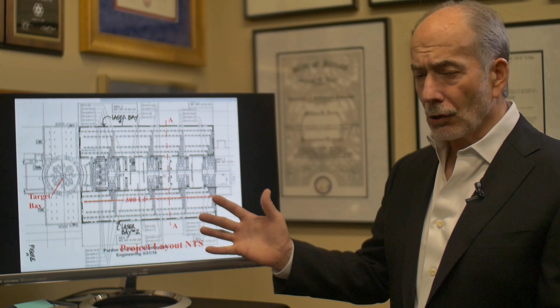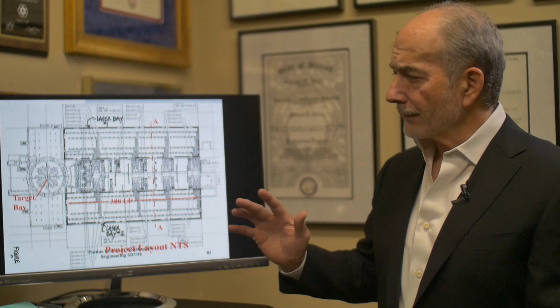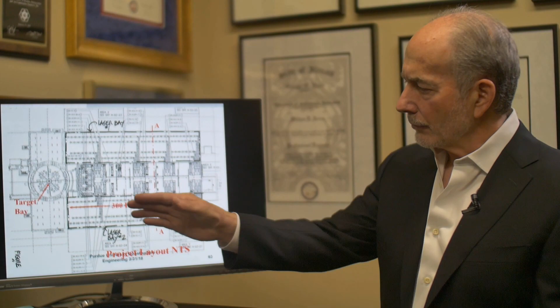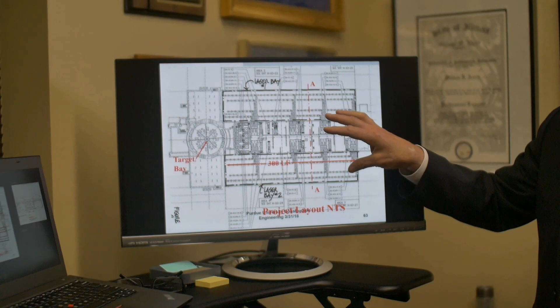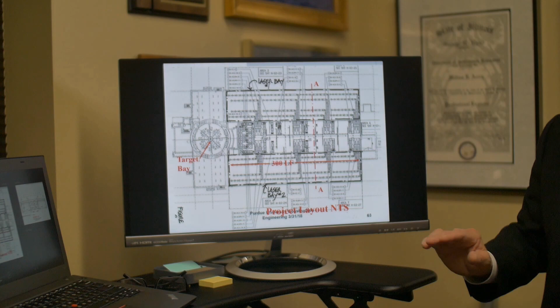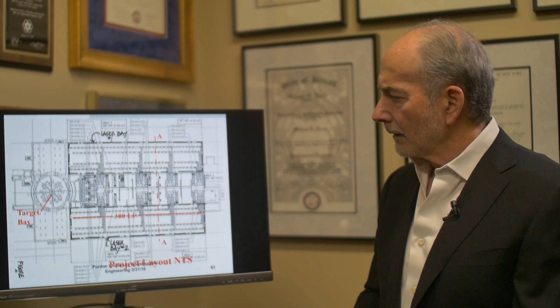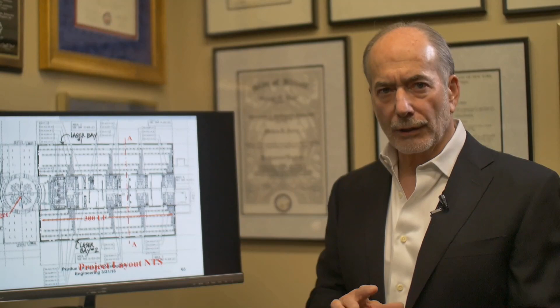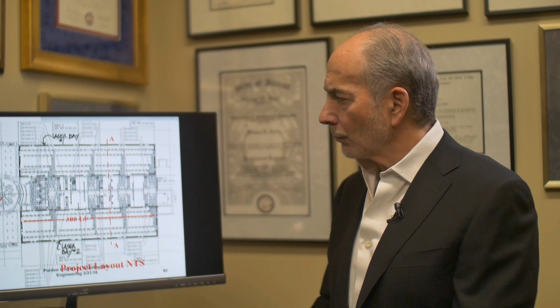This next project is kind of a fascinating project. It involves the largest laser facility in the world at the time of its design and construction for the Lawrence Livermore National Laboratories, known as the NIF facility, the National Ignition Facility. It involved 2 clean bays, 300 feet long, as you can see, and 50 feet wide each one, and very powerful lasers that focused at a sphere 10 meters in diameter, aluminum sphere, 10 meters in diameter, with the hope to do fusion. The challenge on this project, I was brought in during the construction because they were determining that the environmental control requirements of the facility, temperature, humidity, vibration, and acoustics, were not being met.